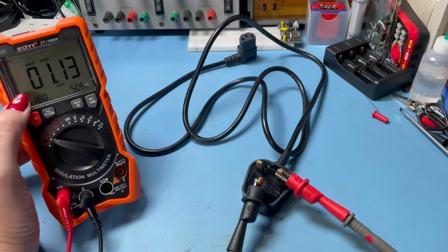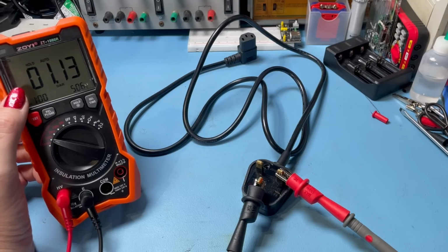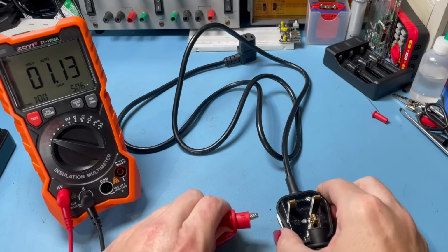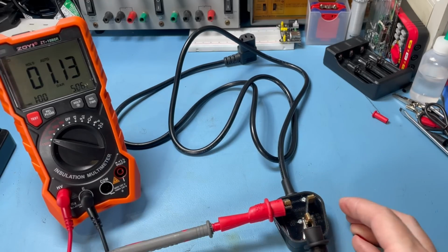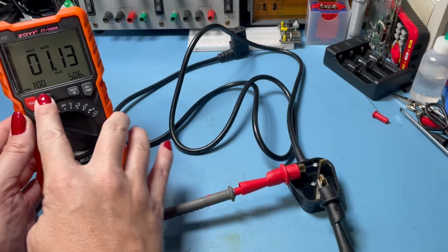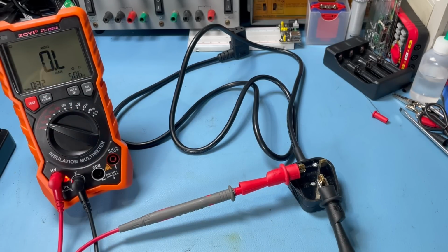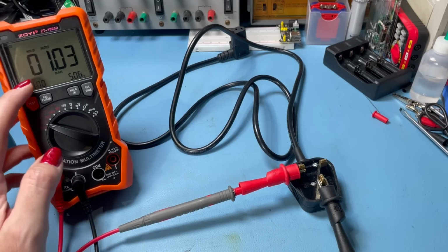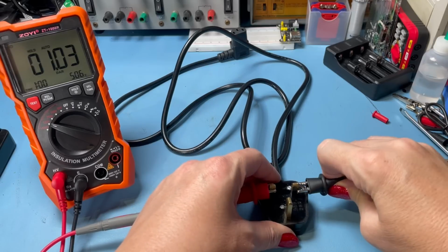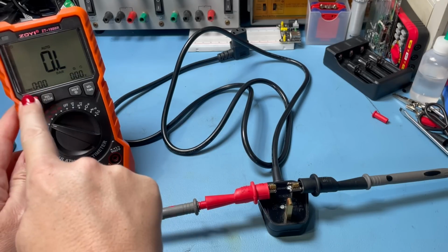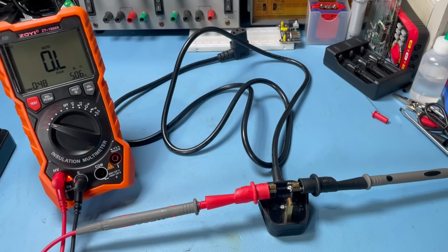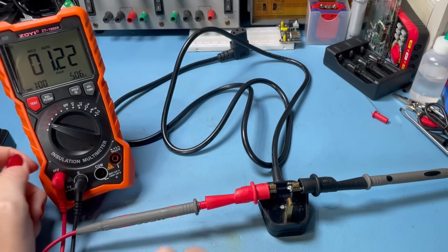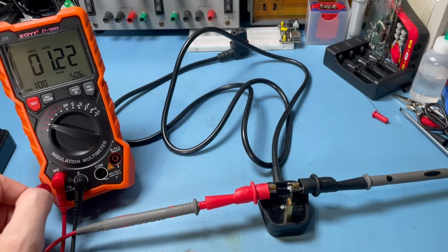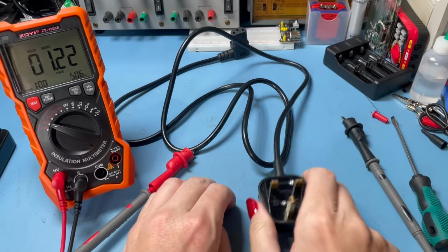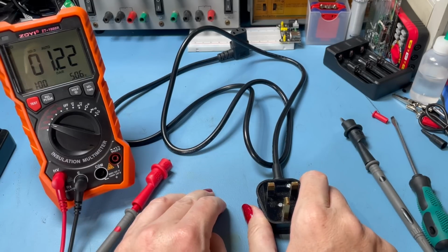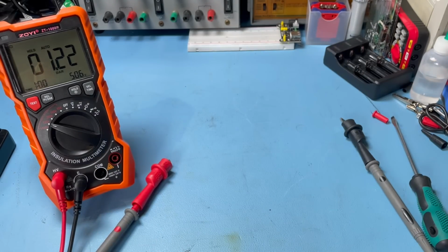So that's quite interesting. We've got a DAR of 1.13 there, so the PVC insulation performing better than the rubber. I'm quite interested now to see how the insulation tests on the other pins. Okay, let's repeat that with neutral to earth and see where we go. 1.03. That's interesting. One last test on this is the live to neutral test. 1.22. So there you go. That proves that the PVC insulation is more effective on this kettle lead than the rubber insulation on the other kettle lead that we tested. Now, without an insulation tester, we'd have never known.